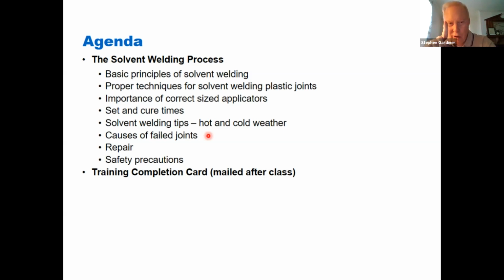Number one cause of failure, though, is not enough solvent cement. And the reason is inertia and the way your wrist works with gravity. When you're applying the primer and cement on the pipe end, you're going to lose contact on the bottom. You'll have a U shape with primer and cement at the bottom and nothing up above. Rotate the pipe. Make sure you have an even coat all the way around the circumference of the pipe end. If you can't rotate the pipe, bring your elbow parallel to the pipe, and that will maintain contact of the dauber head or swab head, whatever applicator you're using.